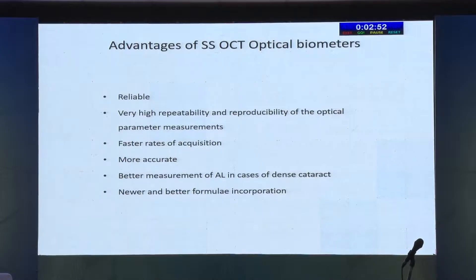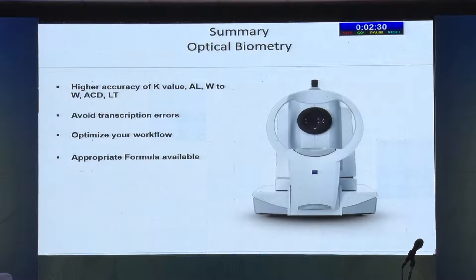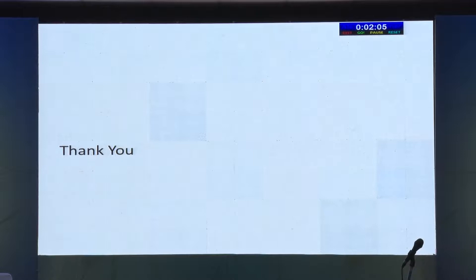Putting all of this together, the best source to get the best results would be a swept source optical biometer of any brand — highly reliable, highly repeatable, fast acquisition, very accurate, better measurements of axial length even in dense cataracts, and newer formulae incorporated. What you get is accuracy of K value, axial length, white-to-white, AC depth, lens thickness, no transcription errors, optimized workflow, and appropriate formula. Playing devil's advocate: you can work a little harder, spend maybe 5–10 minutes more per patient, and get almost the same results with a manual keratometer and ultrasound biometer.